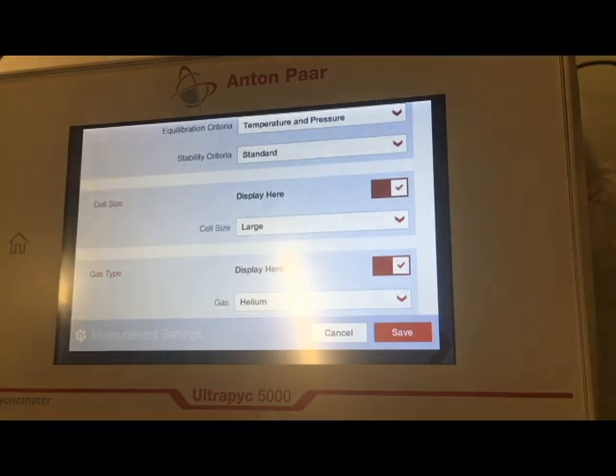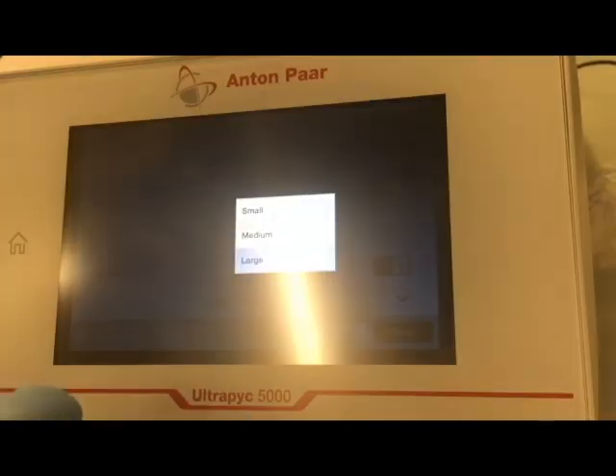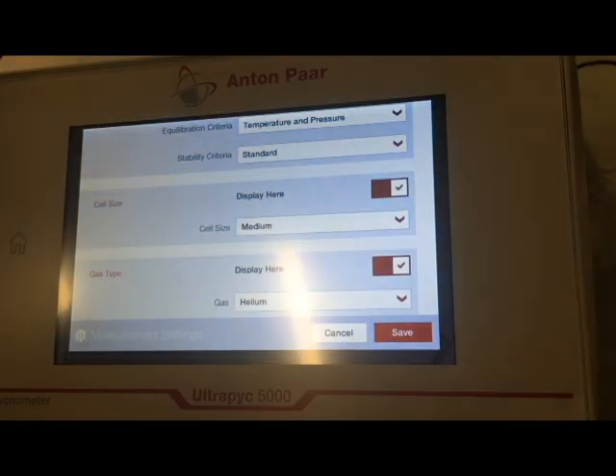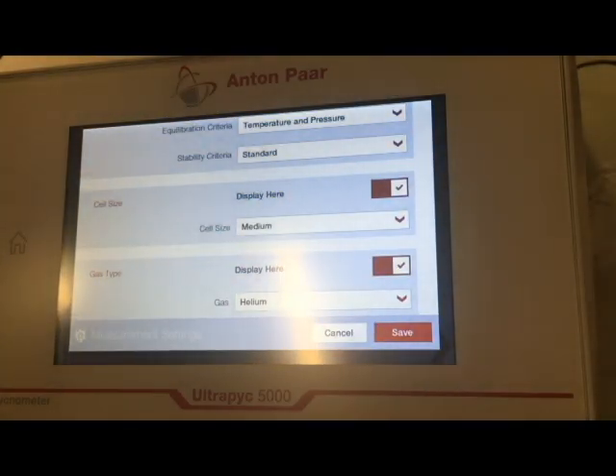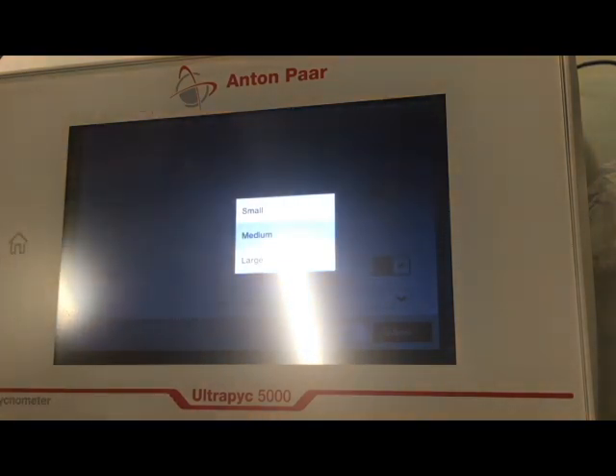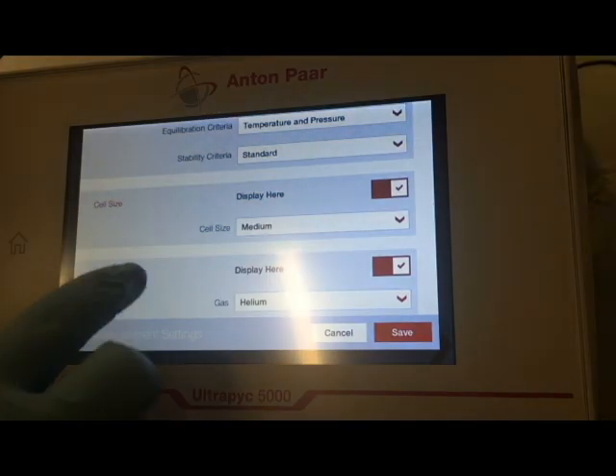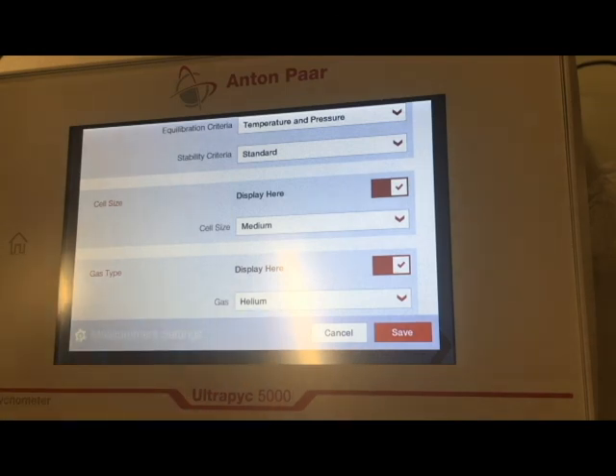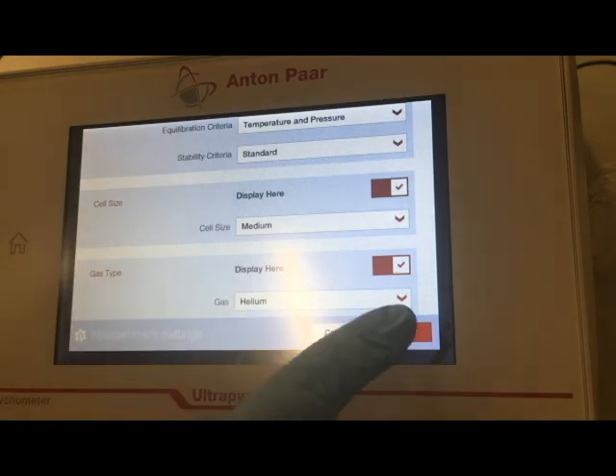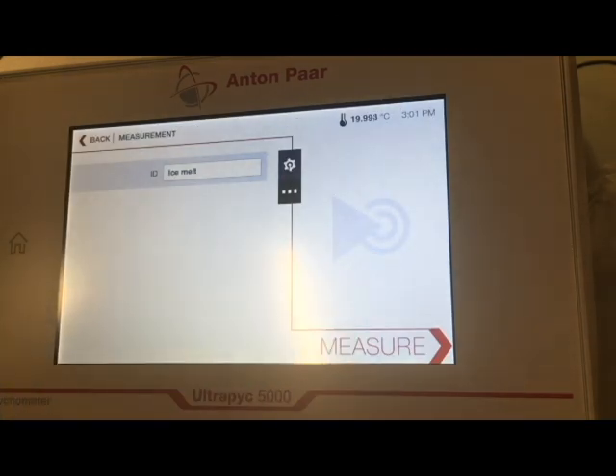Next is cell size. We're going to choose whatever we just calibrated. So we just barely calibrated the medium cell, so we're going to use the medium cell size. If you're using the micro, meso, or nano cells, you should have calibrated to the small option, and you would want to select that one for your run. Gas type is helium. We only have helium as an option here. And then we'll click Save.